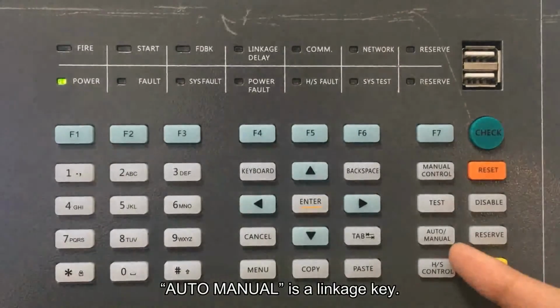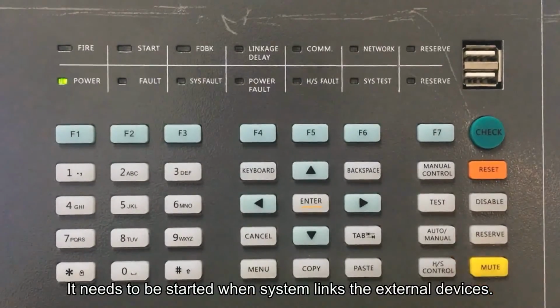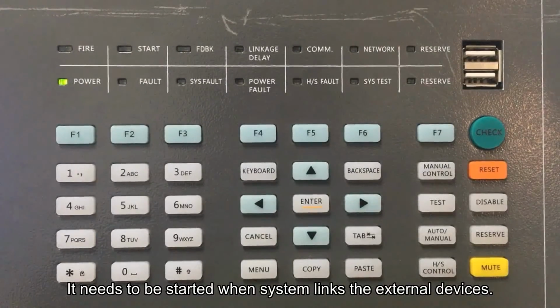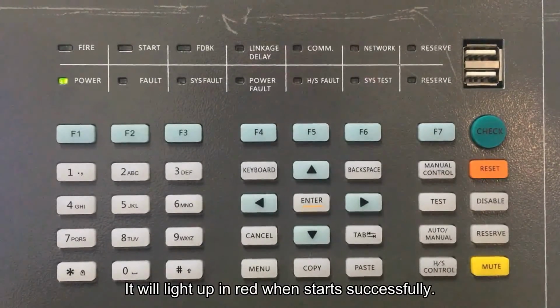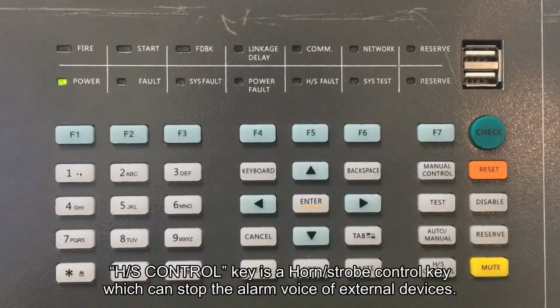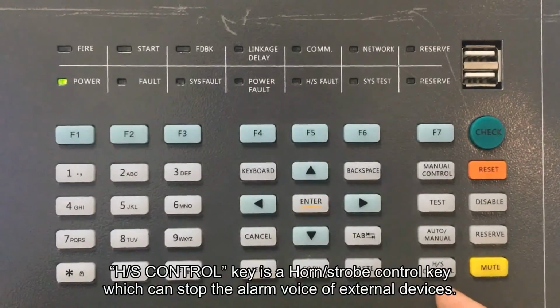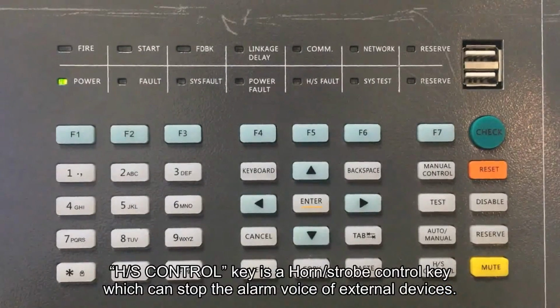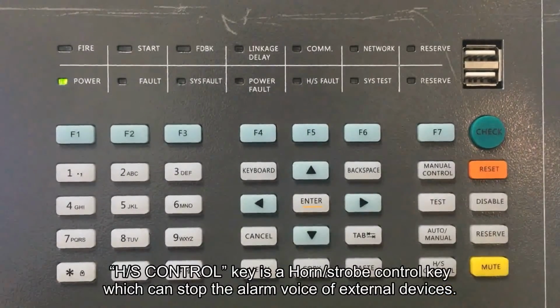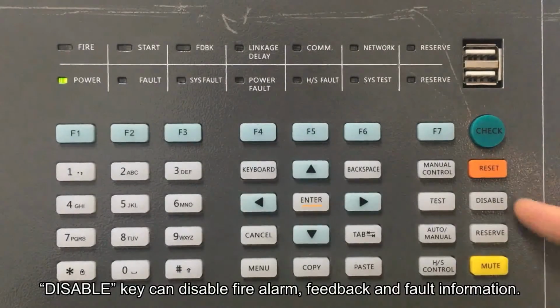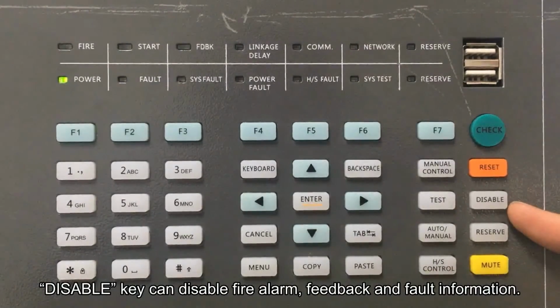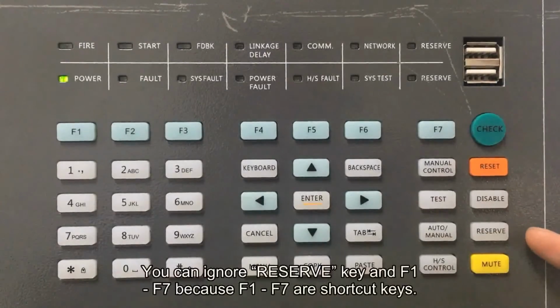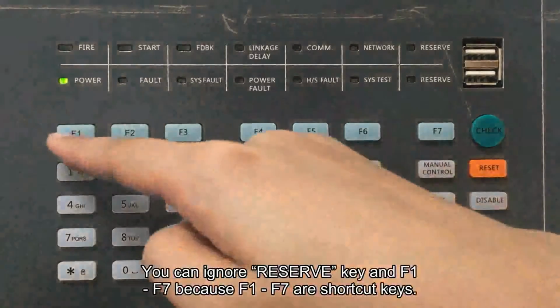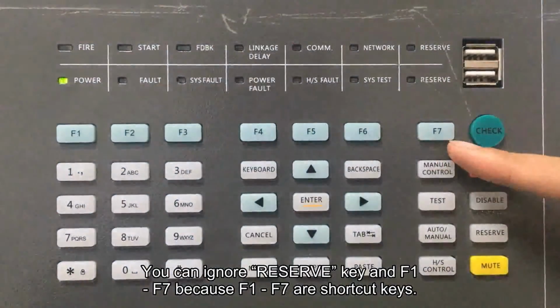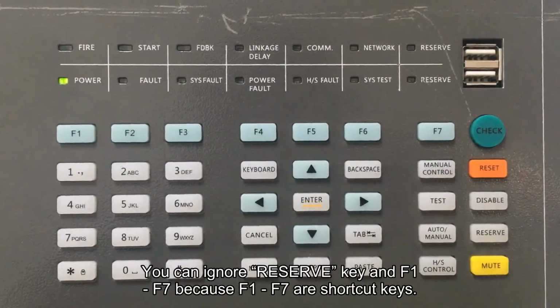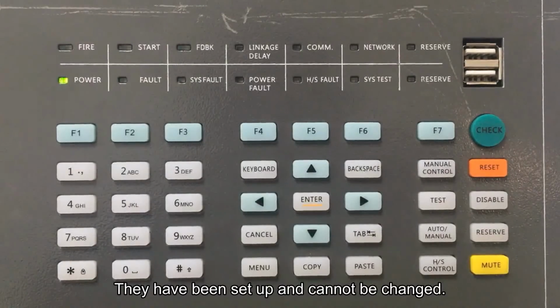Auto manual is a linkage key. It needs to be started when system links to external devices. It will light up in red when started successfully. H and S control key is a horn and strobe control key, which can stop the alarm voice of external devices. Disable key can disable fire alarm, feedback, and fault information. You can ignore reserve key and F1 to F7 because F1 to F7 are shortcut keys. They have been set up and cannot be changed.